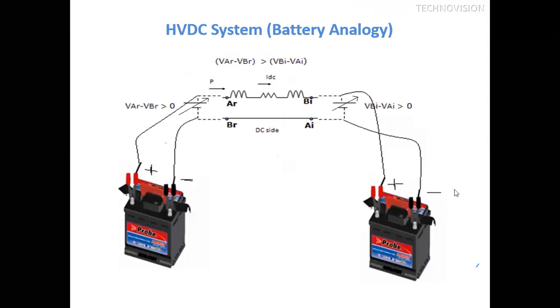So if we take the HVDC case, HVDC we can simply explain with the battery analogy. Suppose there are plus and minus terminals of one battery, and the other is also plus and minus, but this battery is a variable battery. So our HVDC system actually behaves like a variable DC source. The rectifier acts as a source which is variable; by controlling the firing angle, we are controlling the DC. Here also it acts like a battery, and in between there is a smoothing reactor, the resistance of the line, and a smoothing reactor at the other end. When there is a potential difference from rectifier to inverter, current flows: when VAR minus VBR is higher than VBI minus VAI, then current flows from rectifier to inverter. So with the battery analogy, there are not many complications in the HVDC system. It is simply a battery system.